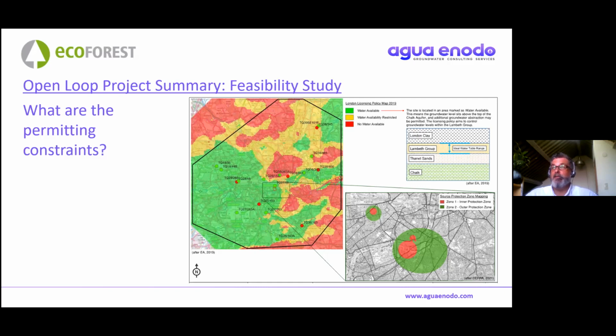It would be a lot easier if we just took the water out of the ground and dumped it in a river, drain or sewer, because then we'd never have to worry about hydraulic and thermal interference between the wells. But the reason best practice and most regulators insist we put the water back in the ground is because this makes our systems resource neutral. We have no net abstraction.